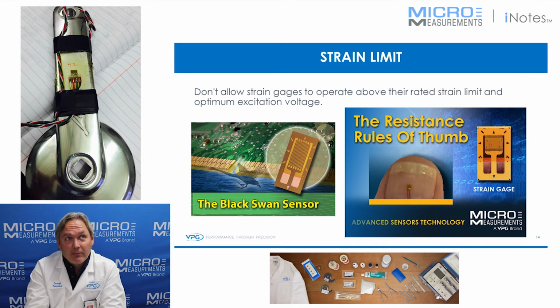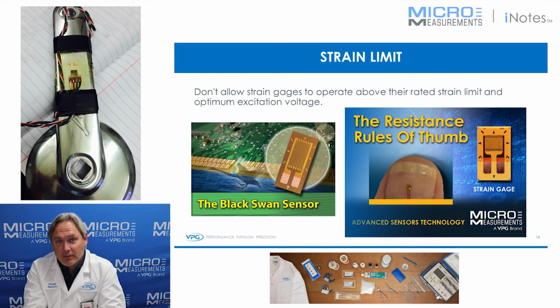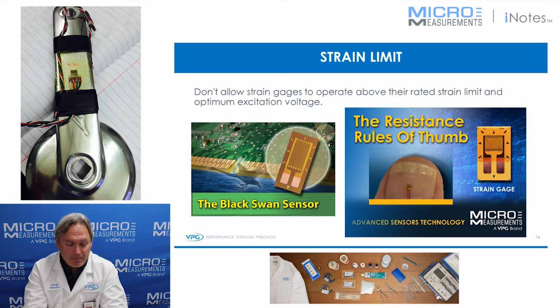If you do, you may run into some fatigue of the strain gauge. They're going to be rated. You can find that published in our catalogs. Typically, if you start operating a strain gauge above about 2,000 microstrain for a lot of cycles, then you need to start being concerned about what the fatigue life is, and some gauges are better in fatigue than others.